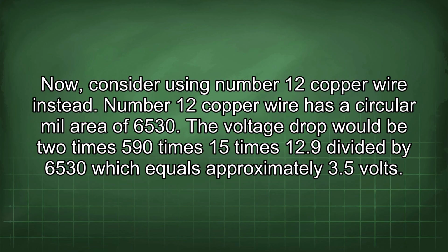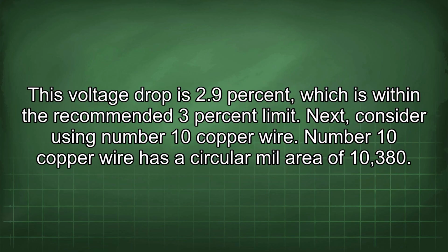Number 12 copper wire has a circular mil area of 6,530. The voltage drop would be 2 times 590 times 15 times 12.9 divided by 6,530, which equals approximately 3.5 volts. This voltage drop is 2.9%, which is within the recommended 3% limit. Next, consider using number 10 copper wire. Number 10 copper wire has a circular mil area of 10,380.